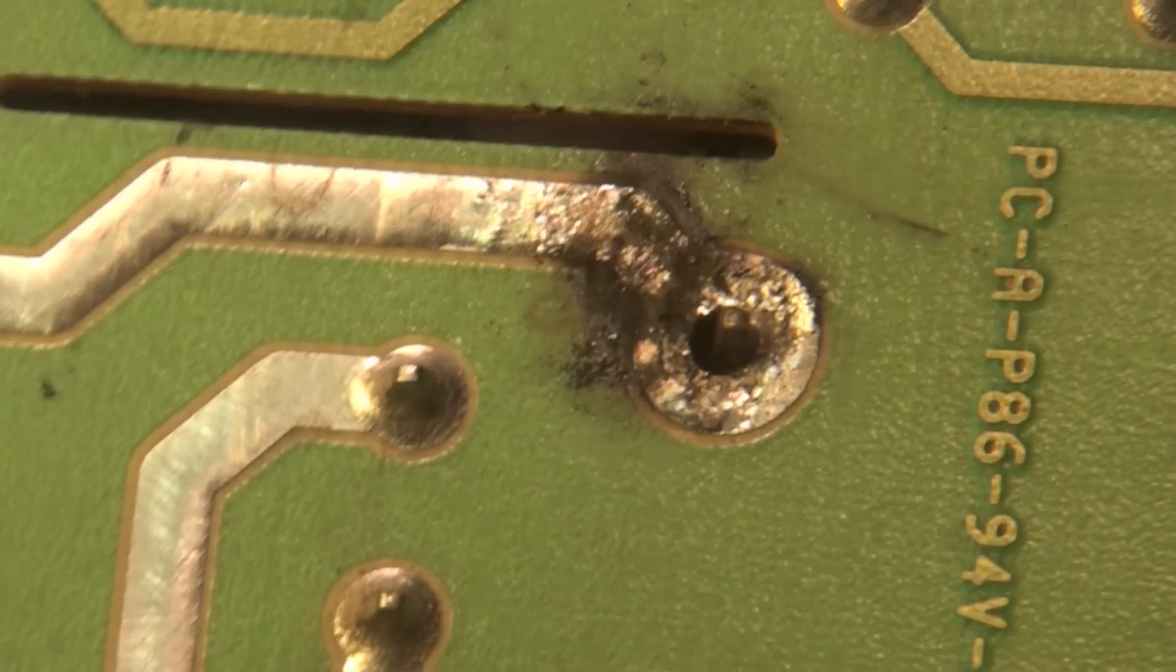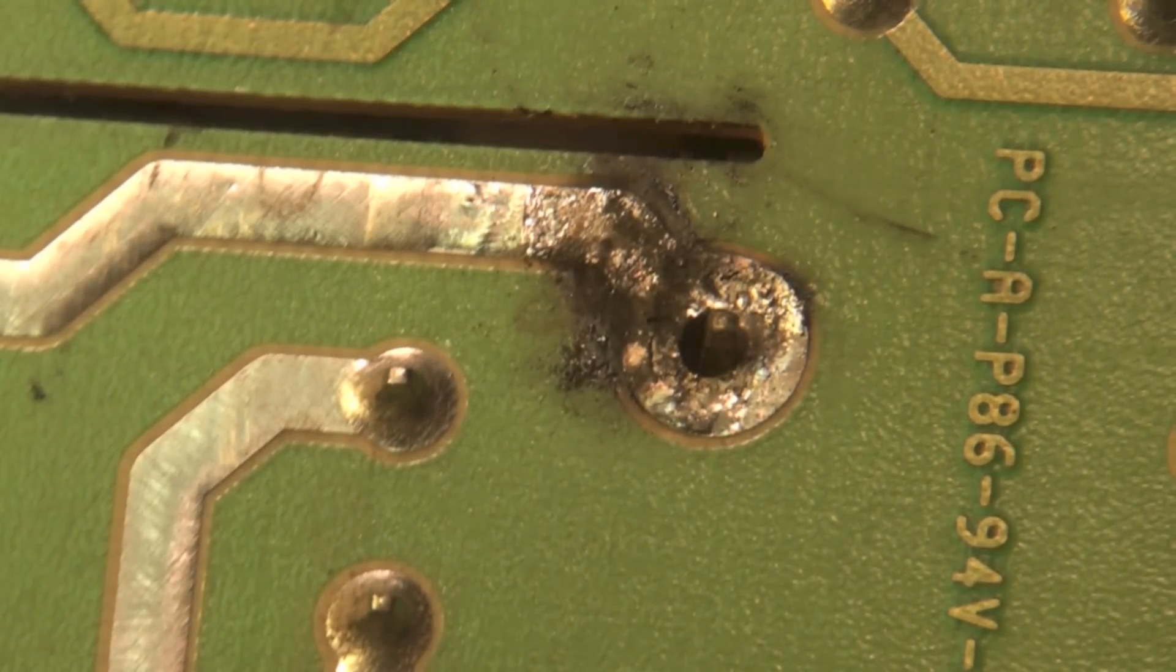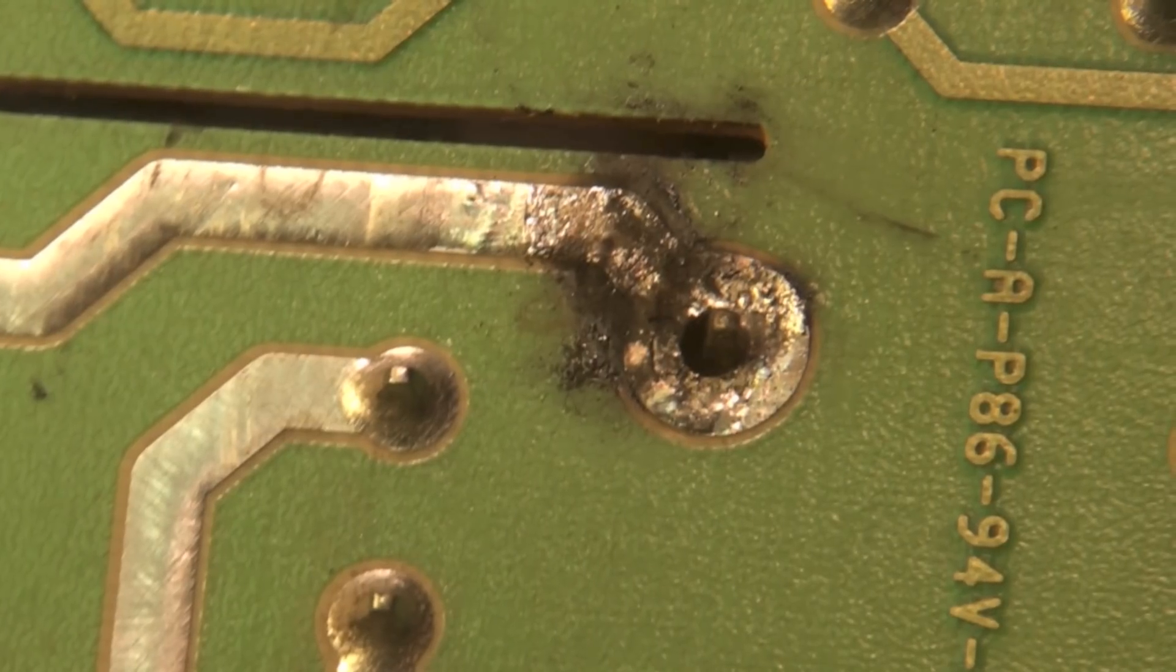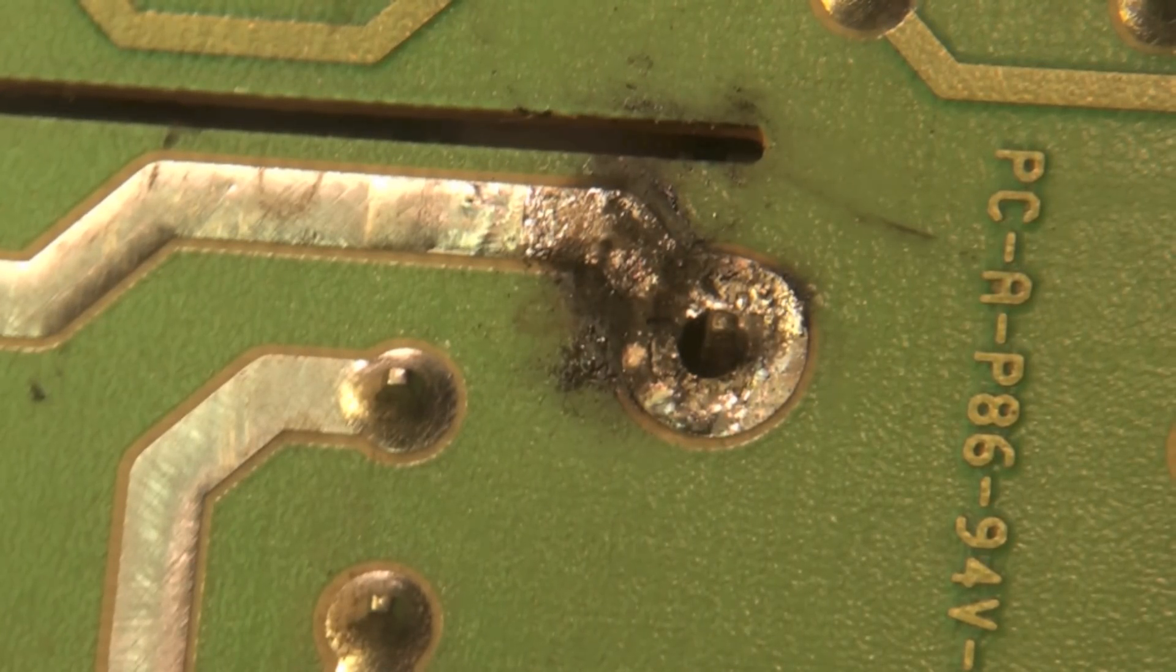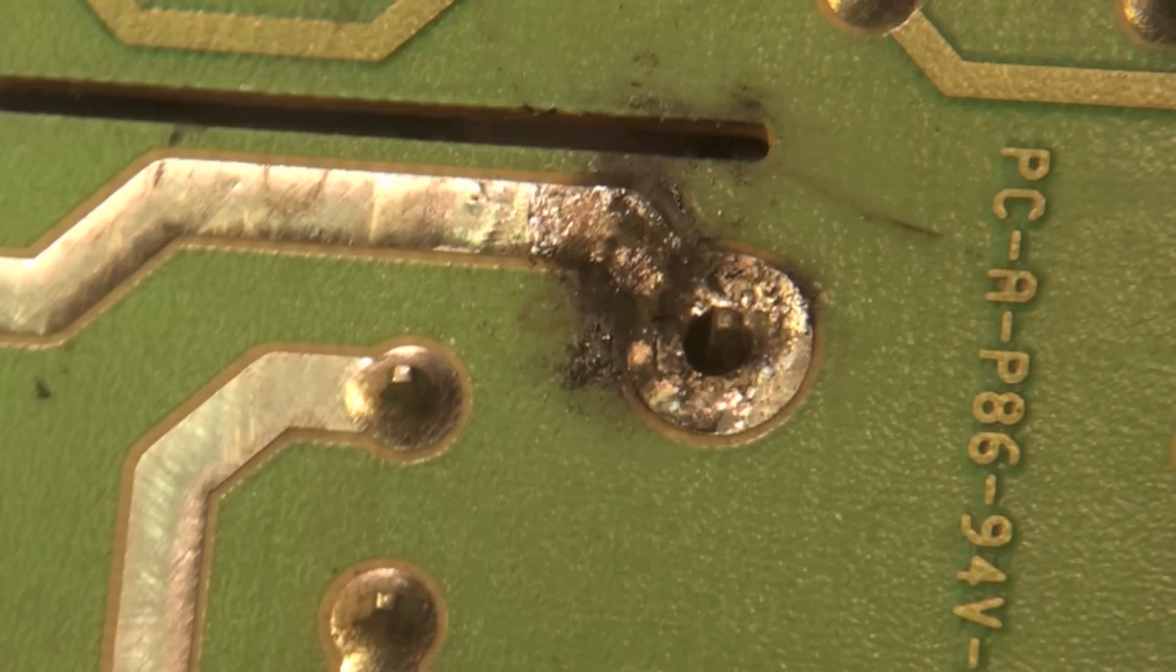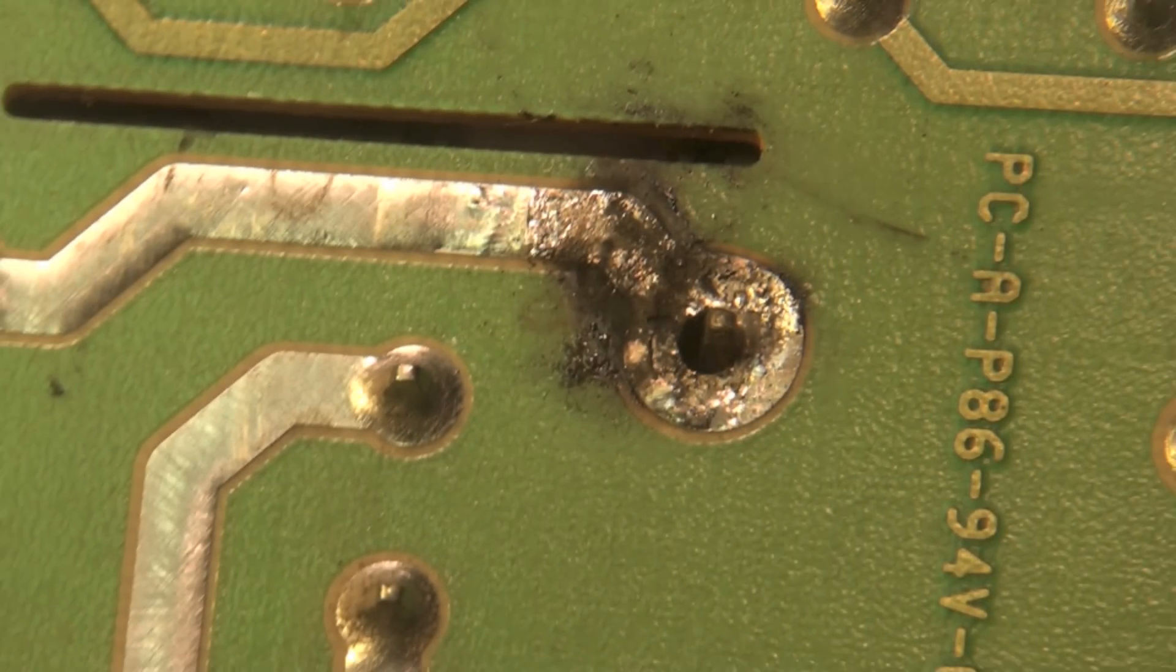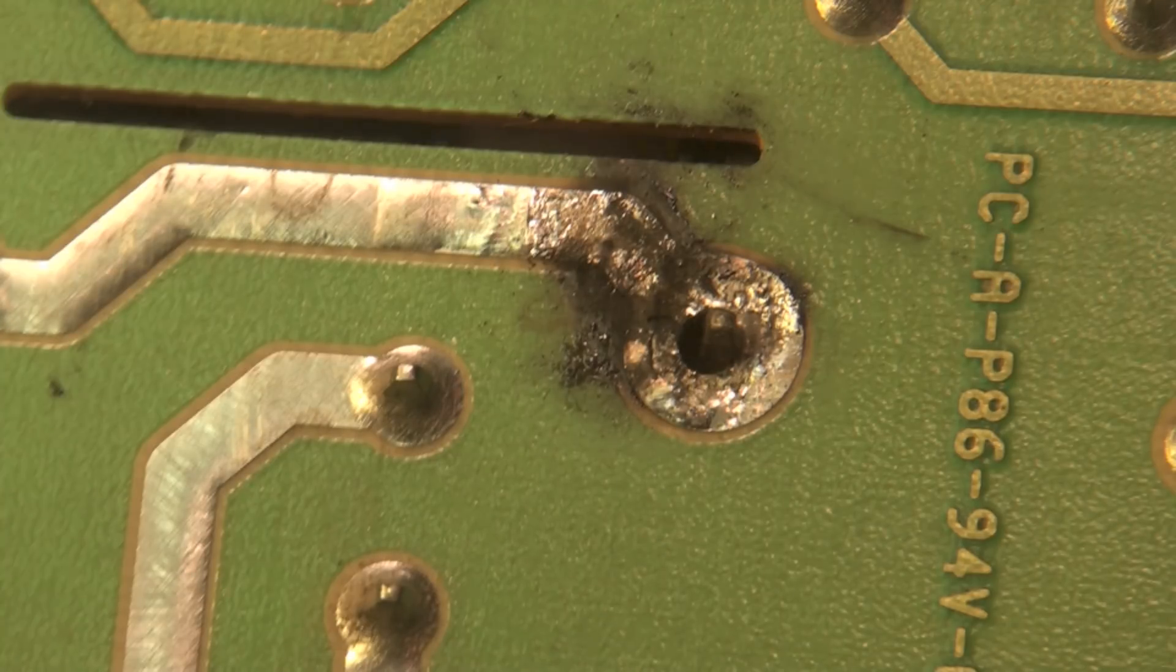When you're finished, go ahead and fire this board back up. Make sure you run it through all the safety tests. Let it go out on flame safety, make sure it shuts down normally under all running conditions. That's a repair of the IFC.